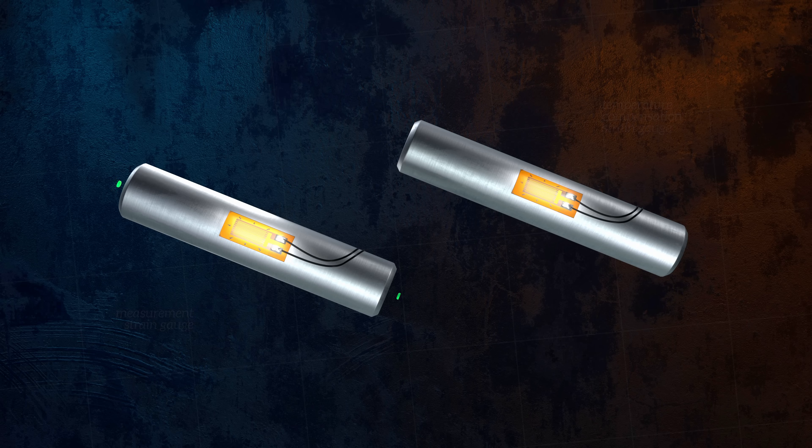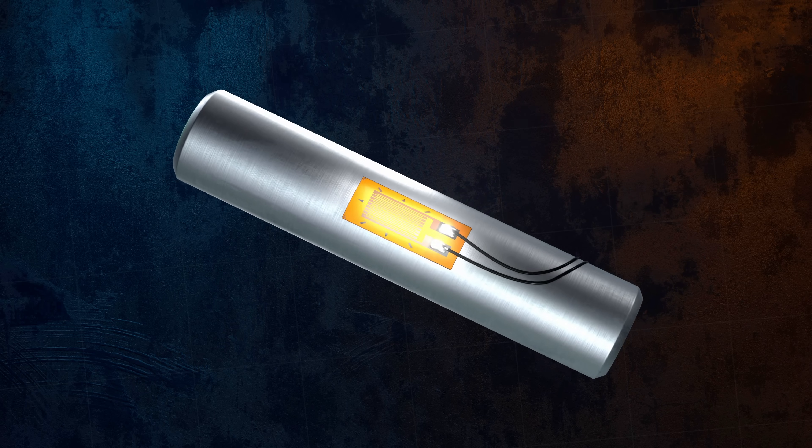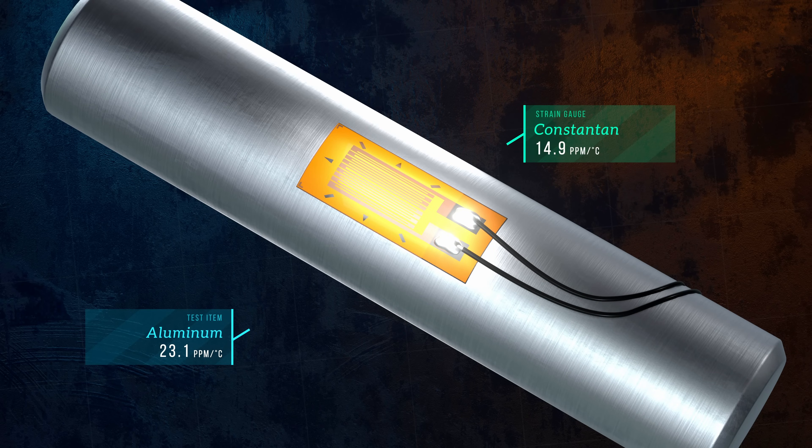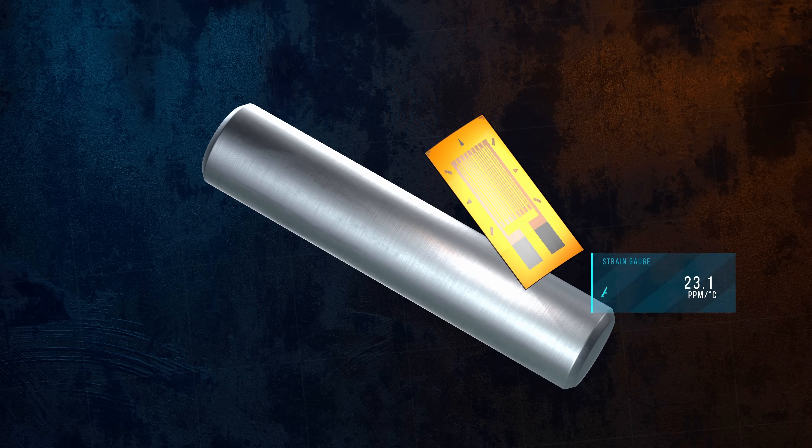A simpler approach is self-compensation, where the strain gauge material is selected to have a CTE similar to that of the test item material. Manufacturers make slight adjustments to the composition of the Constantan alloy, so that they can supply strain gauges with different CTEs. And all you need to do is select the strain gauge with a CTE that matches the test item.